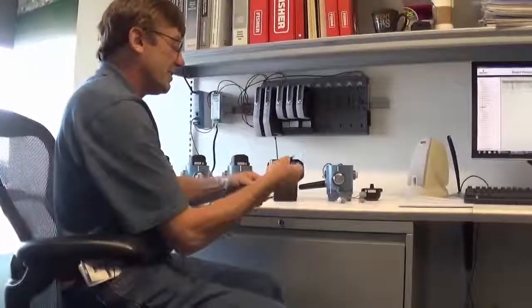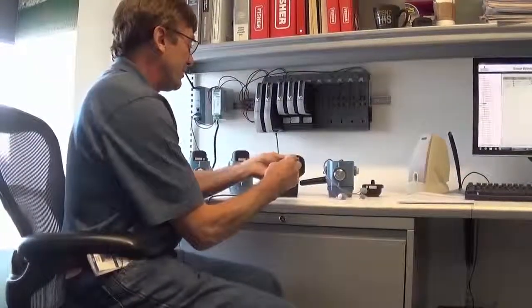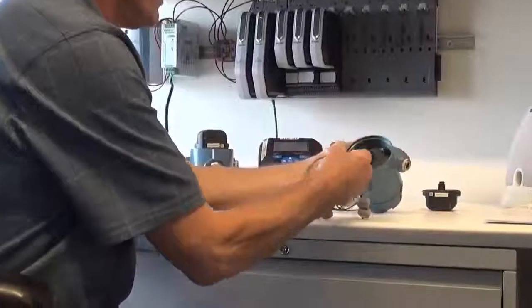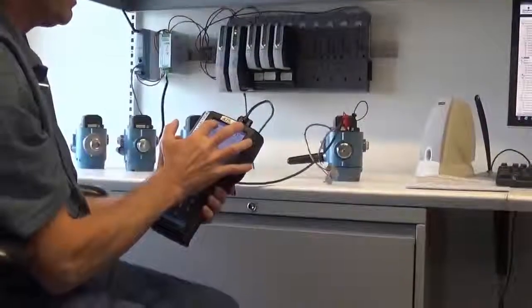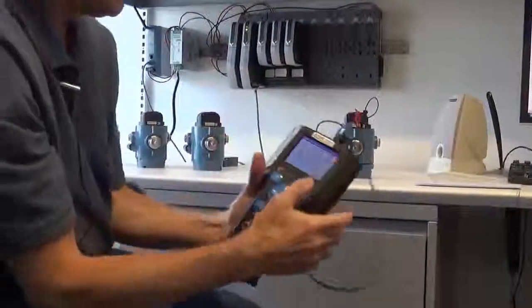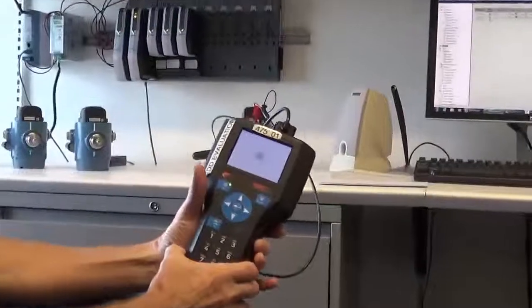First thing I do is connect the communicator up to the device itself, and we're going to use that to set up the network ID and join key. So I'll plug in the battery. At that point we'll go into the device itself using the HART communicator.